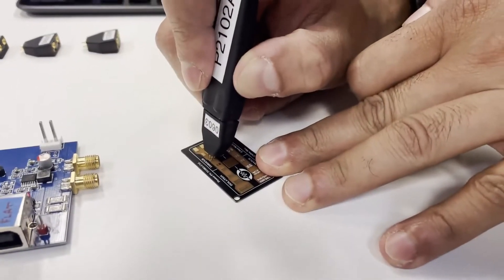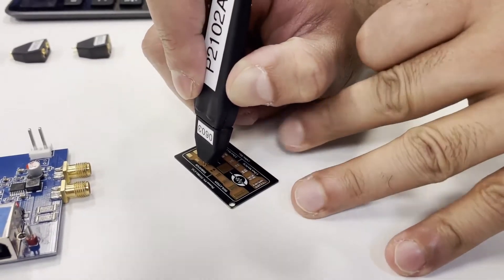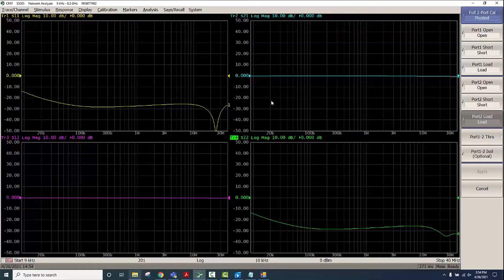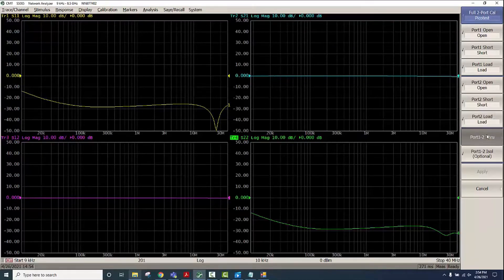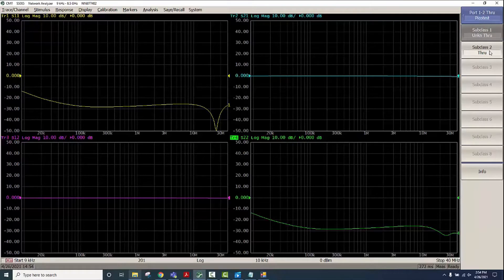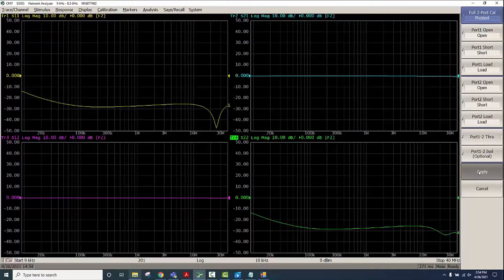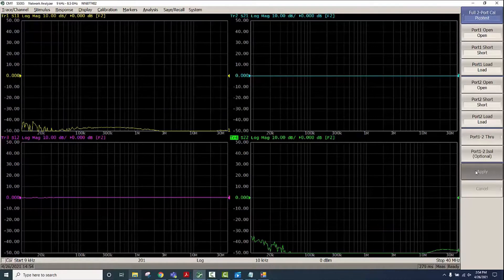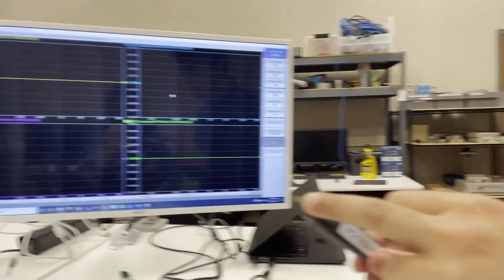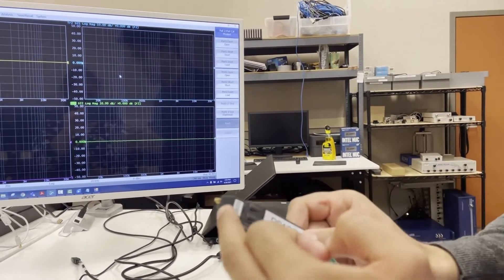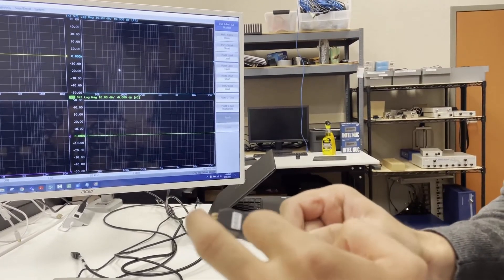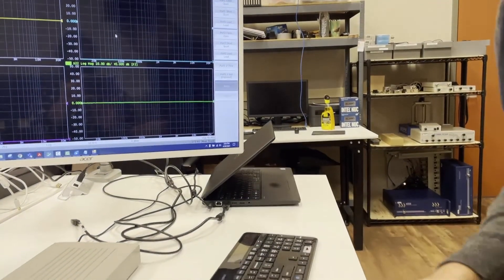The last step is to perform the Through cal. Now we have S21 and S12 close to zero indicating a good through connection and then we'll do Unknown Through. Then we click on Apply. Now the calibration has been performed and the calibration plane has been moved to the end of the probe tips here.